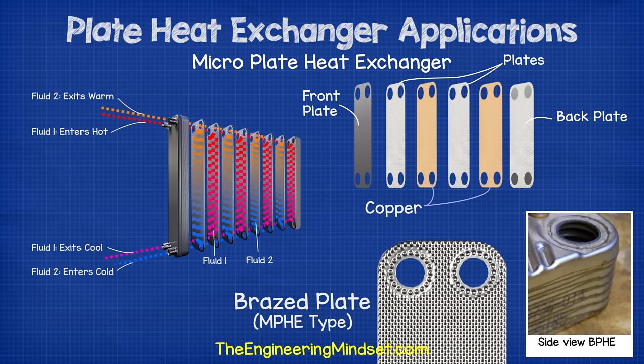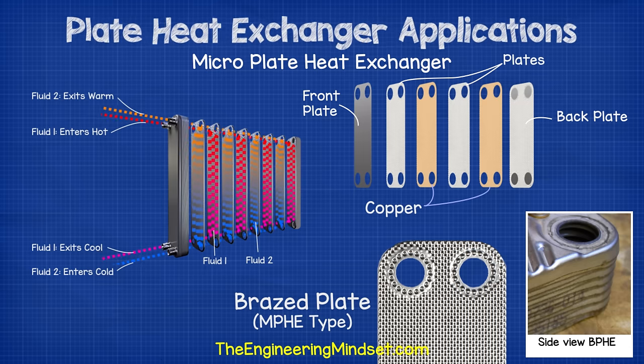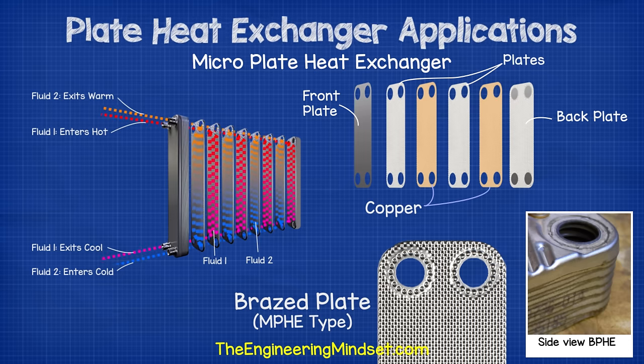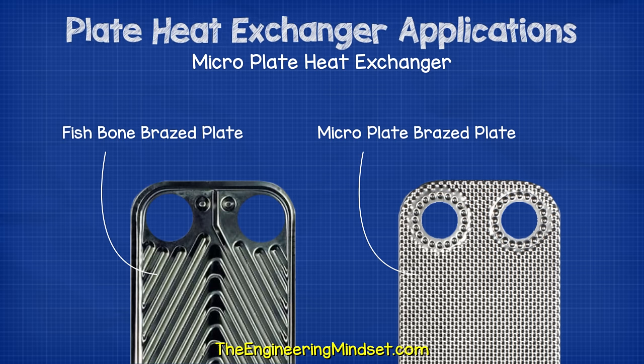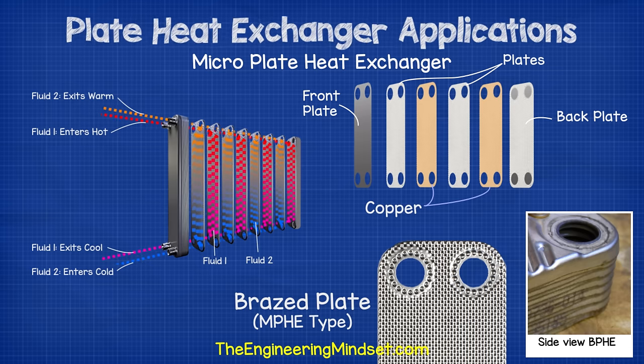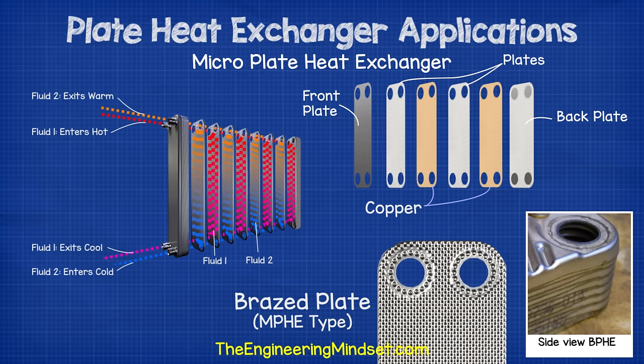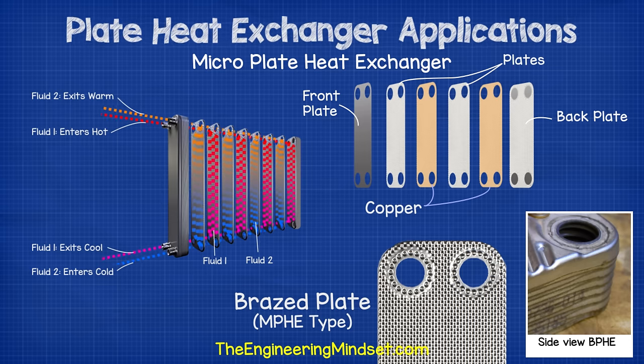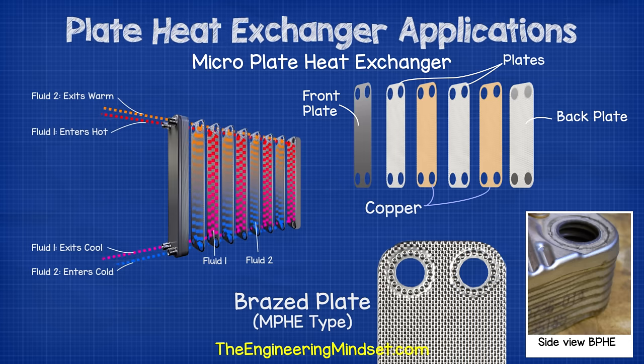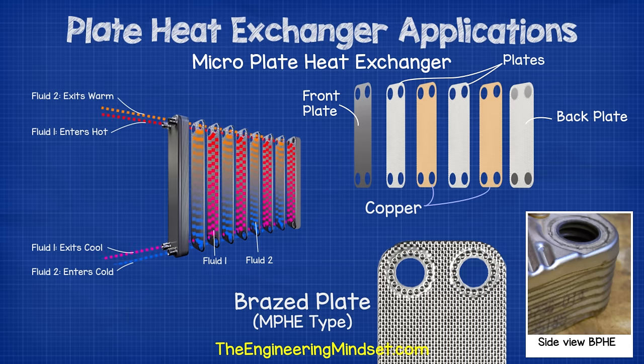Micro plate heat exchangers can be either gasket or brazed plate design and are the next evolution of plate heat exchangers, providing the greatest heat transfer efficiency to date. Standard heat exchangers use a chevron or fishbone pattern pressed into the plate, but micro plate heat exchangers instead use small dimples. This allows the fluids to spread across the plates much more evenly, maximizing heat transfer surface area. It also causes more turbulent fluid flow, which further increases heat transfer. The small dimples increase surface area, allowing more opportunities for heat transfer, and these design improvements allow lighter and smaller heat exchangers to be used.